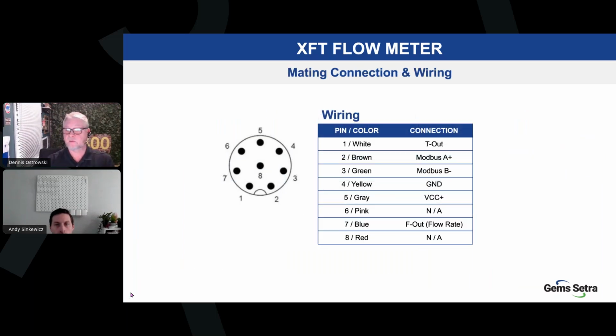Next slide is a representation of the pinout. The highlights here are that you've got a 4 to 20 temperature output, you've got a 4 to 20 flow output, and then you've got your Modbus communications. Okay, next slide.